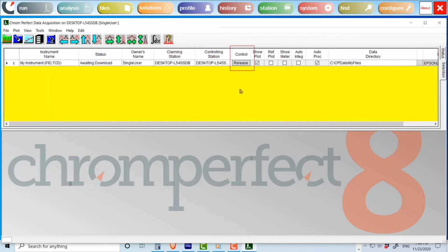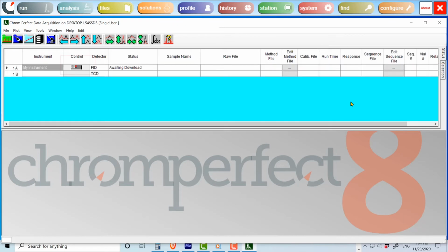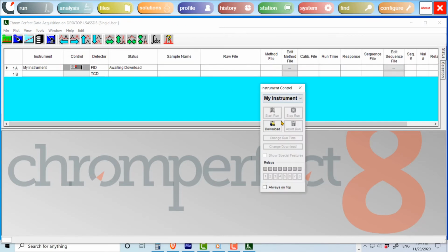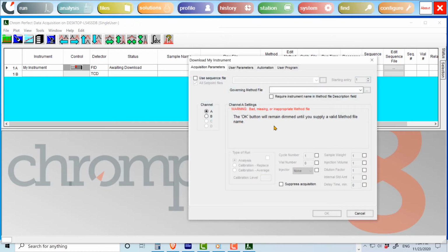To control an instrument, first you must claim it. Go to the Control column and press the Claim button for an instrument and move the cursor away. After a second or so, the button caption will change to Release. This is your confirmation that the instrument has been claimed. Next, click the Status tab on the right, and the spreadsheet with the blue background will appear. Clicking the Control icon brings up the instrument control form. Click on the Download button to download your method. This form has several tabs, but for now, we need only concern ourselves with the Acquisition Parameters tab section.